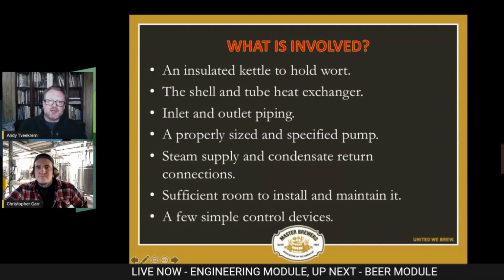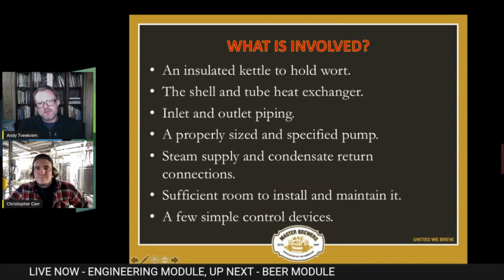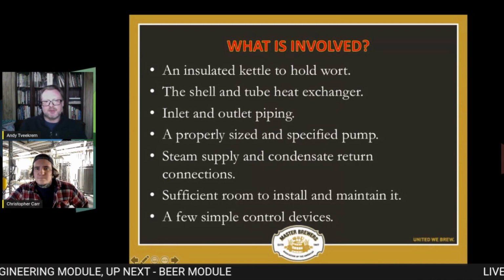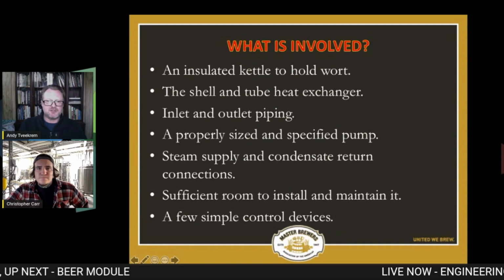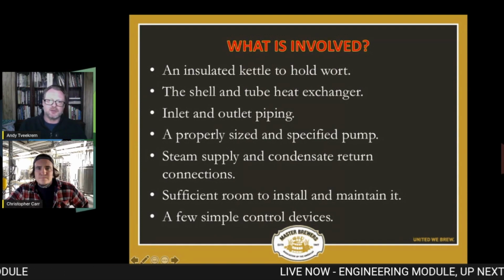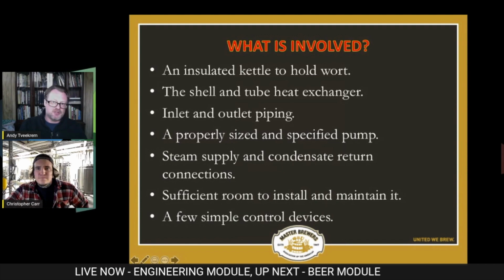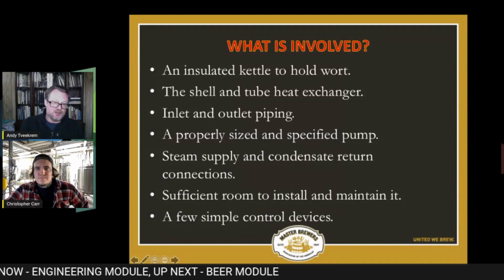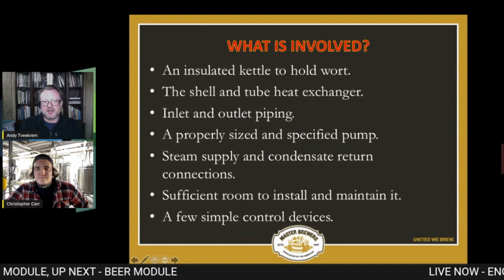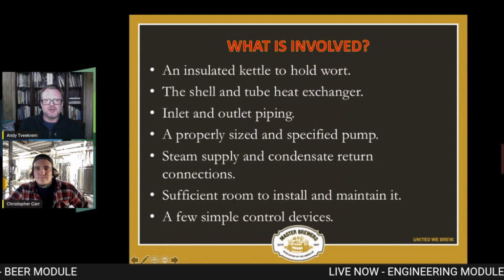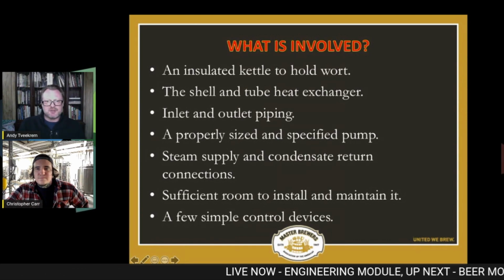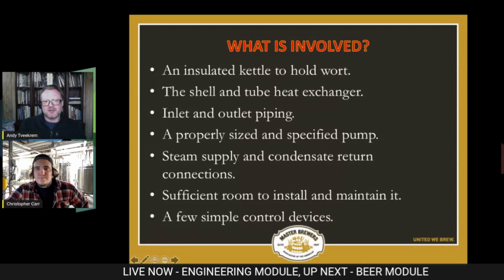You've got the inlet and outlet piping, and you need a pump. That's probably the biggest disadvantage to these compared to internal calandrias - that you do need a pump. Although I'm seeing some internal calandria designs that also involve a pump, so they're kind of losing that advantage. But the pump's got to be properly sized and specified, and we'll talk about that in a second.